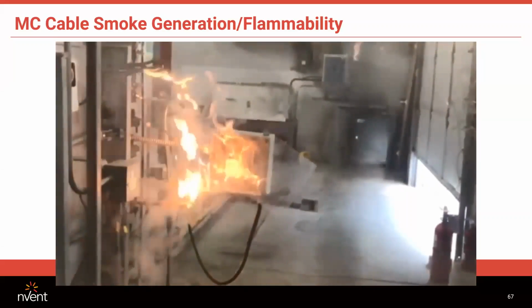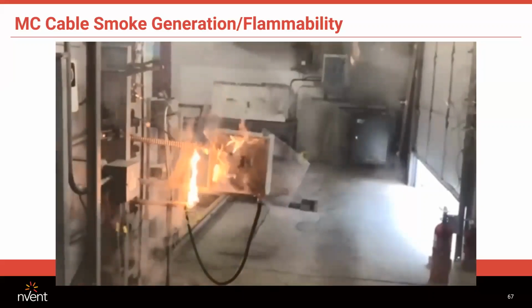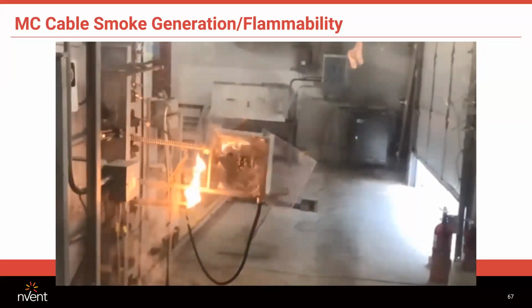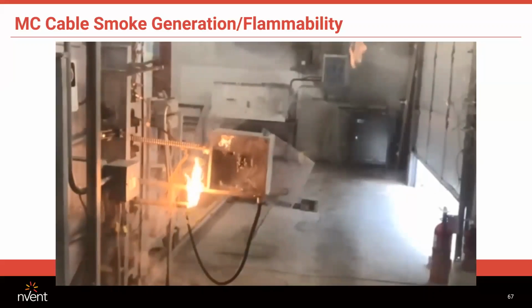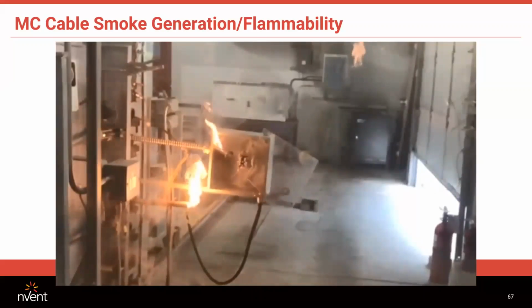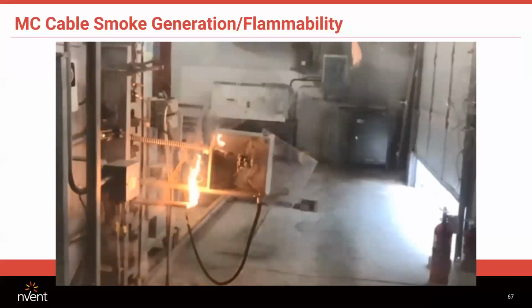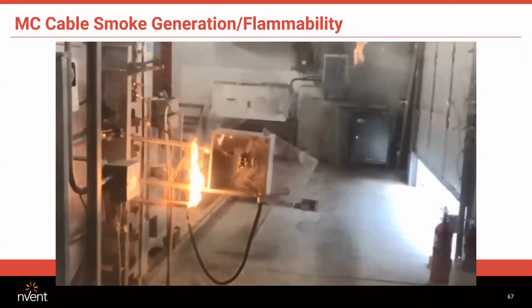There's a contactor in that box, and look what happened. Something like that happens, you lose all your gear, you lose your emergency power. This is something, as I mentioned, engineers, I'm in Massachusetts. Massachusetts is really ground zero for fire-rated cable because they were the first in the nation. And this is good to know in case you ever have to be doing work here. Massachusetts requires 2-hour fire-rated feeders in all buildings, regardless of height or occupancy.